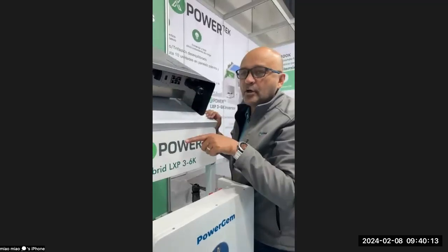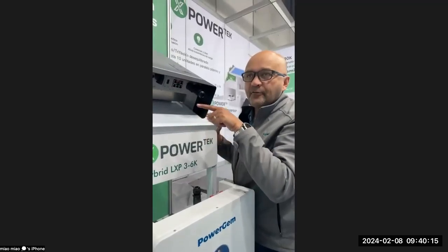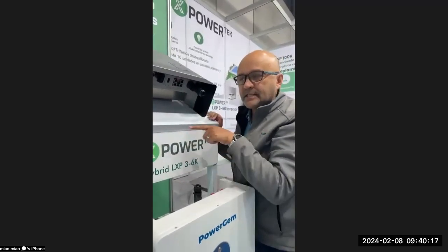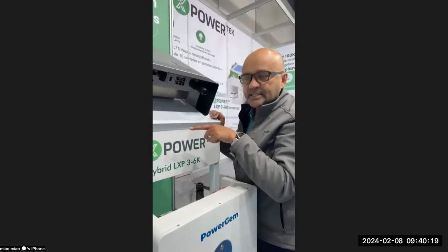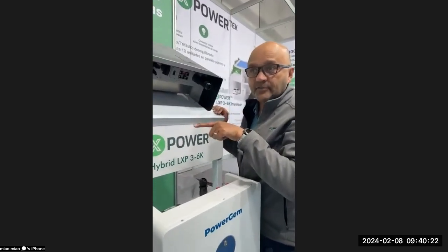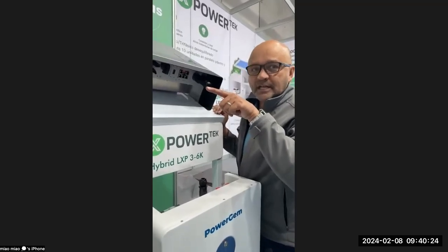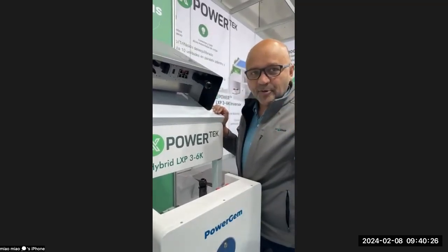If you have a look at machines that already have more than 5 kilowatts installed, you'll see that at the start of the day, when it's supplying the load and charging the batteries, the curve climbs, and the minute the batteries are charged, it will flatline and then taper off at the end of the day.